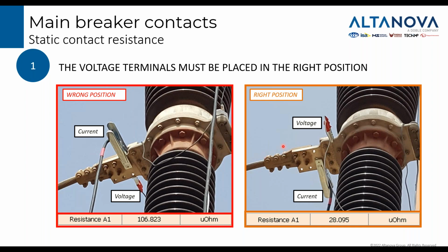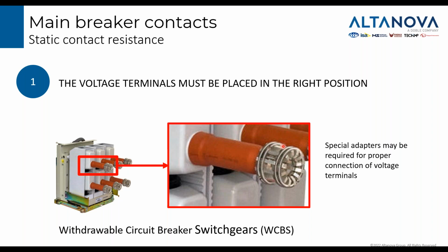So a good practice is that maybe you can take a picture of the first measurement, and the second time you try to repeat the same measurement. By looking at the picture, you will place the clamps in exactly the same position. So the values that you are getting are comparable. In the case of a medium voltage circuit breaker, the concept is the same, but maybe you can find a situation like this. So it's difficult to place the clamp always in the same position. It is suggested to have adapters in order to guarantee the best repeatability of the measurement.